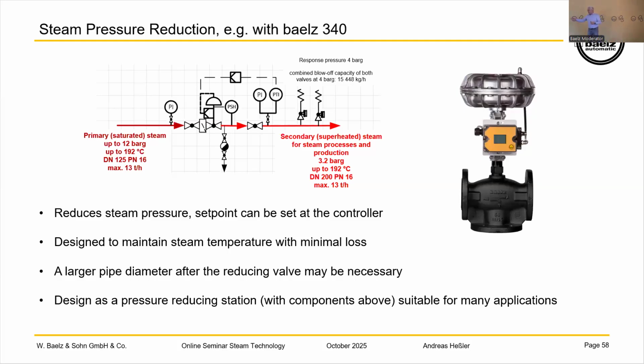Another question. The turn down ratio of the control valve. This is a good question. It depends on what kind of control valve, and also on what kind of characteristic you have, linear, parabolic or equal percentage. In the normal case, for stroke valves like the ones we use, you can say between 1 to 30 up to 1 to 50. It depends a little bit on the valve, but this is normally the turn down ratio.